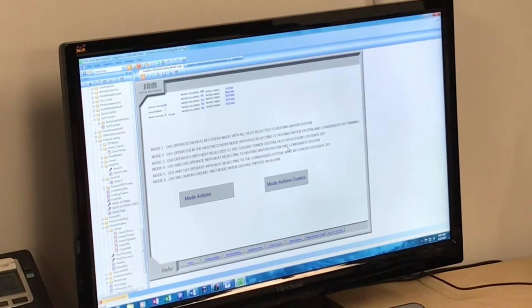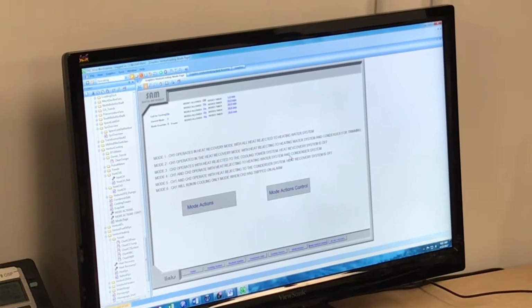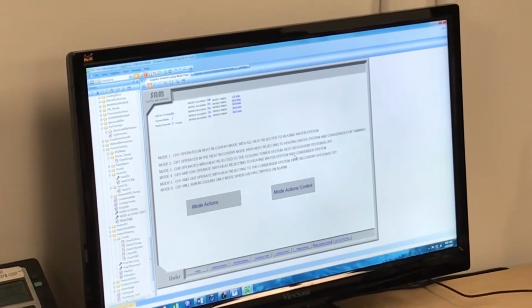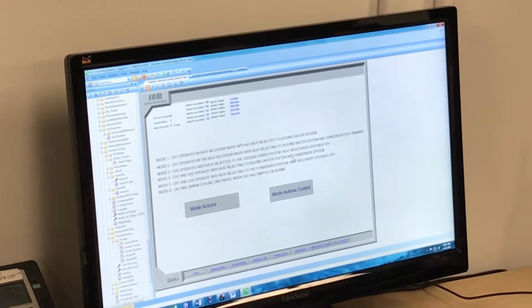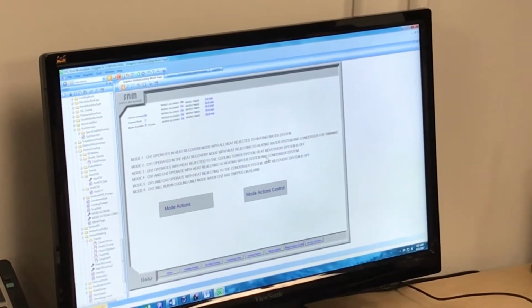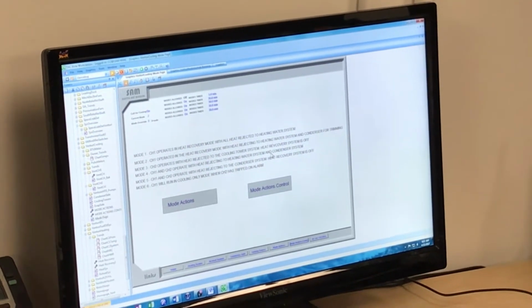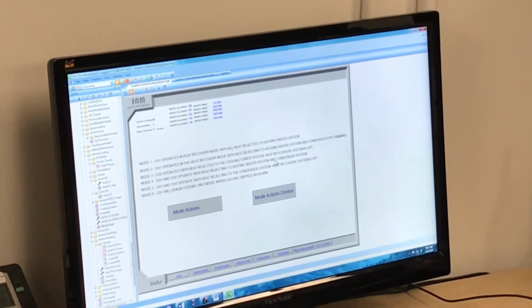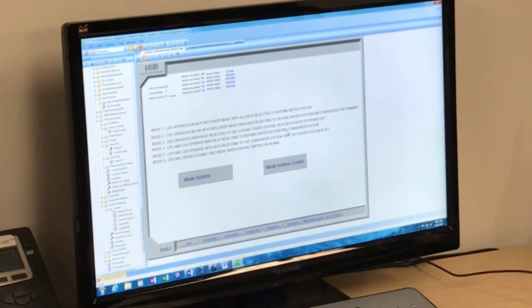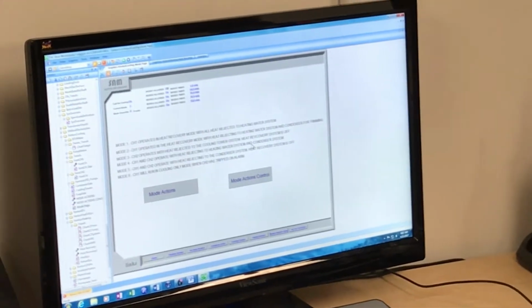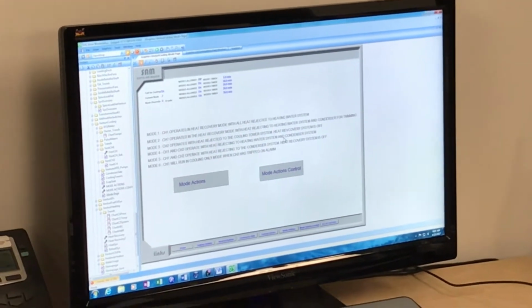And the split will be done internally through the program. They have some calculation adjusting the set point, so that they will split the load somehow. So mode 4 covers both demands, cooling and heating, usually. Yes, cooling and heating, when there's a high cooling load. Otherwise, chiller 1, the mode 2, will be sufficient.